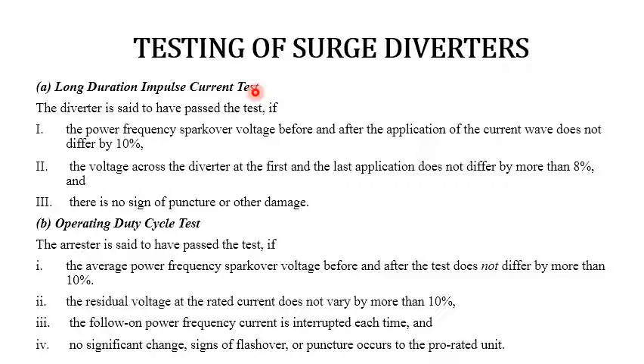It is usual to record the waveform in the first two and the last two applications of the current wave. Then the diverter is said to have passed the test if the power frequency spark-over voltage before and after the application of the current wave does not differ by more than 10%, the voltage across the diverter at the first and the last application does not differ by more than 8%, and there is no sign of puncture or damage after applying the current pulses. Then we say that it has passed.